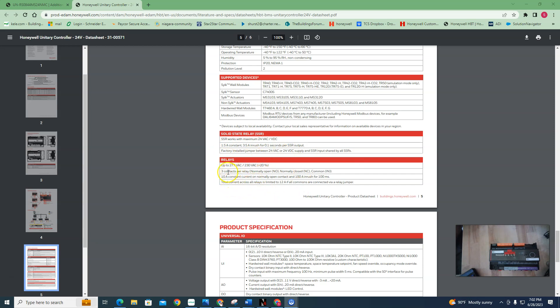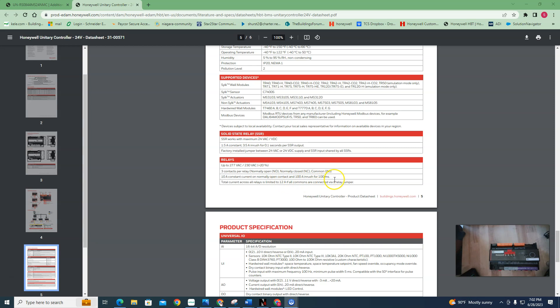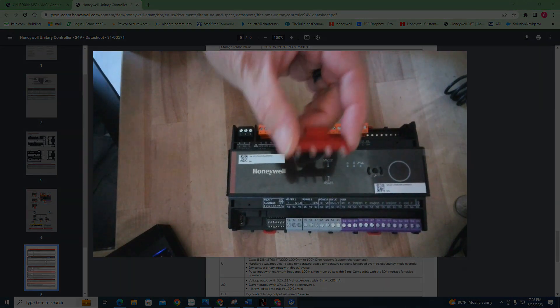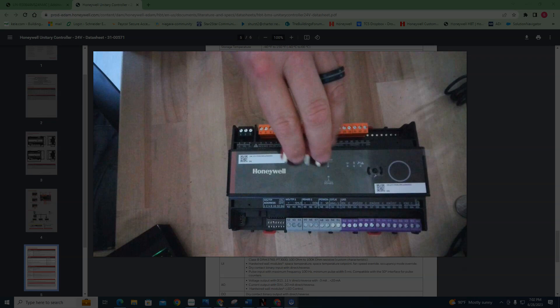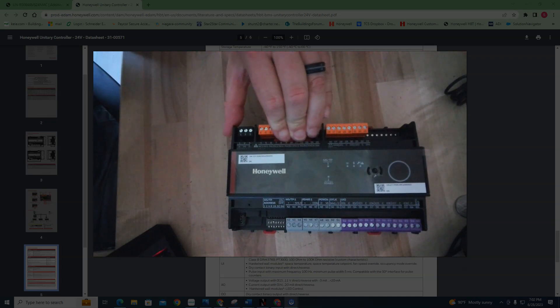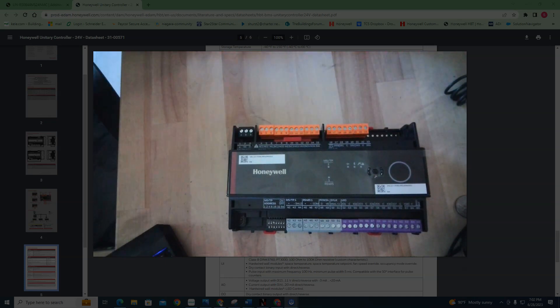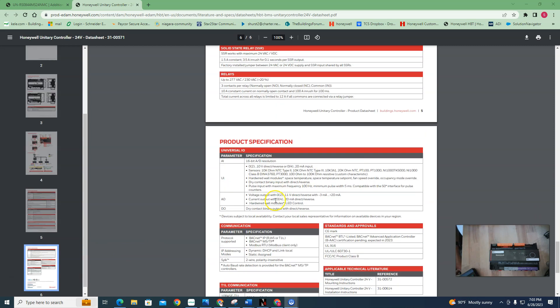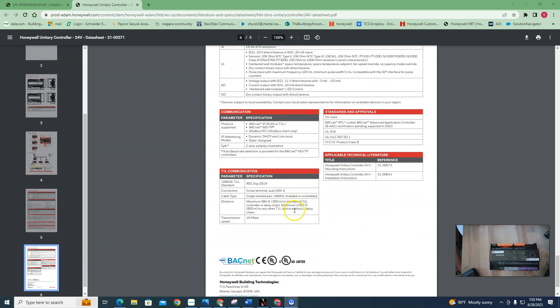But your relays - this is the star of the show right here. Your relays can pull in up to 277 volts AC and you get three contacts - normally open, normally closed, and common. You got a 10 amp constant current on normally open contact and a 100 amp inrush for 100 milliseconds. That's heavy duty. But you have a little uh-oh down here - the total across all the relays is limited to 12 amps if you're using this jumper right here. If you have this jumper in, you're limited to 12 amps total. I don't even know what you're going to be bringing into a controller with 12 amps, but I'm safe to say that's pretty heavy duty.